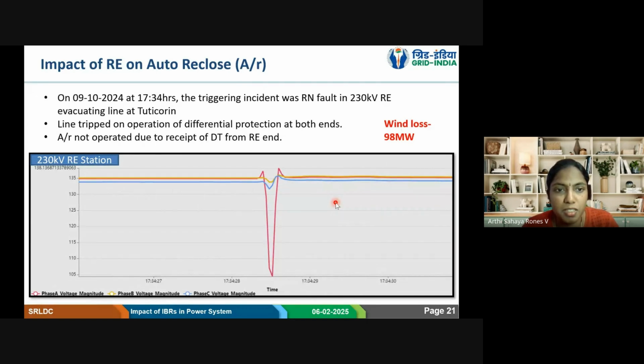But through simulation studies, what we are observing is when you consider an auto reclose condition, during the dead time, two other healthy phases are available. That means your net positive sequence voltage, if we see, is like 67% available. So when you compare this with the LVRT curve, it's well within the curve. So auto recloser should operate, but few RE OEMs are saying there is some issue. Few others are telling it is okay. So that is the thing. When we studied with respect to few inverters in the simulation, it is performing correctly only, and we feel it should be in service. So wherever this auto recloser non-operation is there, we are asking them to enable it, and we are asking them to remove this direct trip sending scheme.